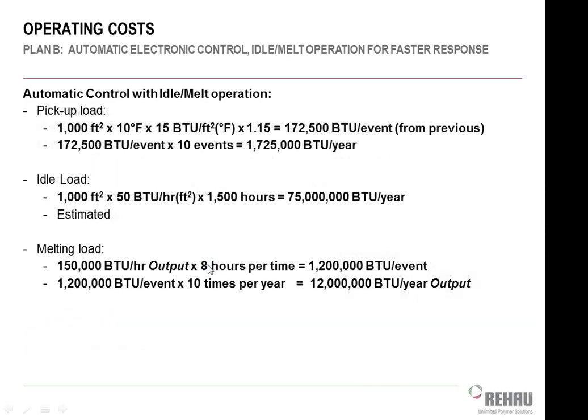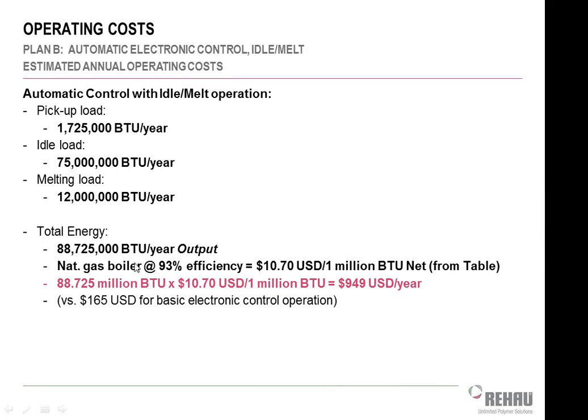So let's skip along to the money part because we're running out of time. So there's my pickup loads. There's my idling load, which is obviously much larger. My total melting load. So the whole thing in this scenario, my pickup load is 1.7. My idling load is 75,000,000 BTUs per year. That's where most of my energy is coming from, to keep that thing idling, which means I can melt the snow faster once it happens. And then my actual melting load is fairly small. But this is costing me about $1,000 a year at $1 a therm to run that kind of system. So it helps melt the snow faster by keeping the slab slightly warm all winter long, keeping it idly warm, if you will.